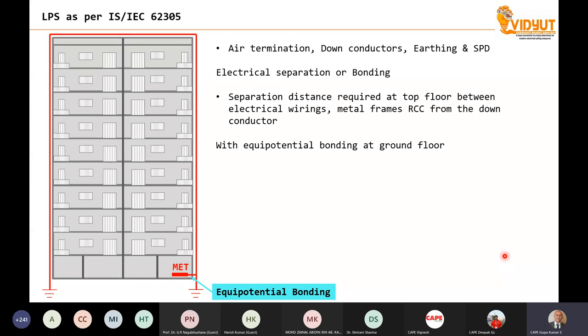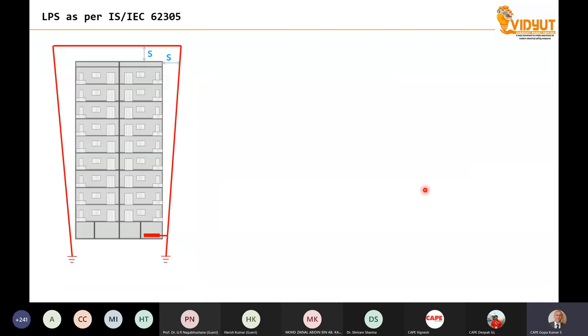Electrical separation means that once the lightning current flows through some of the conductive parts, there is a chance that the nearby metallic parts could be in danger because of a spark over. As a result, we are supposed to measure the separation distance, and the electrical apparatuses shall be kept a little bit away from the down conductor. Now, I am showing you a typical example with the calculation. Let us say, just as an example, 1 meter is the distance between the air terminal and the metallic parts.